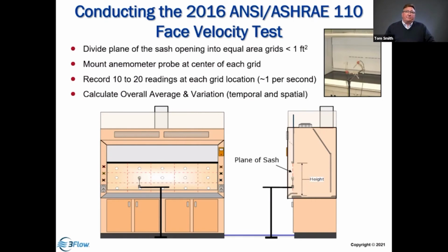So to mount the probe on a stand, we use a microphone stand. Or you could use a ring stand and mount it inside the hood. It's up to you. But the standard says that the probe must be mounted at each of these grids. We divide the opening into equal areas to measure top to bottom, left and right, and then divide that area into equal areas, each not more than 1 square foot. So each grid should not have a side more than 12 inches.